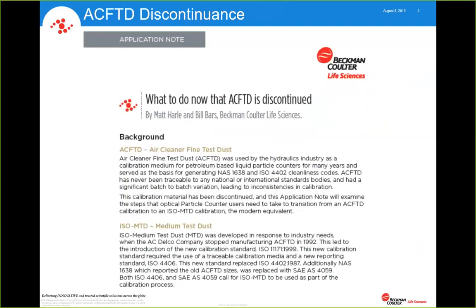So, what to do now that ACFTD is discontinued. Our target date is going to be the end of this year for our commercial users. For those of you that don't know what ACFTD is, the background is air cleaner fine test dust, ACFTD, was used by the hydraulics industry as a calibration medium for petroleum-based liquid particle counters for many years. It came into existence back in the 60s. It was used in the 70s and 80s. And then we got into the 90s, and that's when ISO medium test dust came into effect in 1999. So it's now been 20 years that we've actually had a calibration media that's traceable to NIST. And so we're trying to transition some of our customers that still maintain the AC fine test dust calibrations into the new, more modern calibration method of ISO medium test dust.